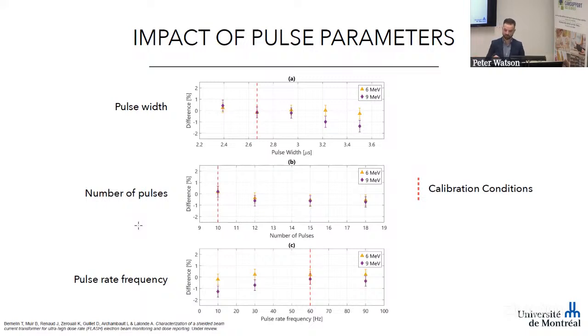For the 9 MeV beam, we see a little drop in the accuracy, so the agreement between the BCT and the alanine. And this directly comes from what I've talked about earlier. The energy changes with pulse width. So depending where your calibration point is on your PDD, if you're in a region of higher gradient, you might just be more sensitive to that. So we don't think it's the BCT reporting the wrong dose. We just think it's the dose changing, basically.